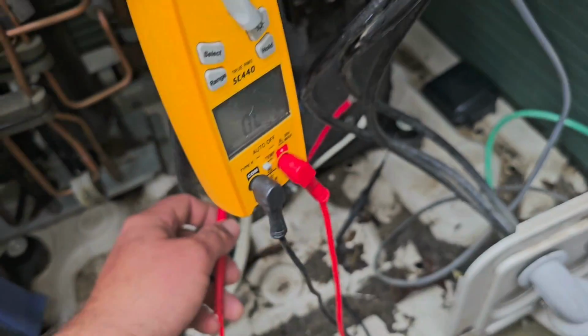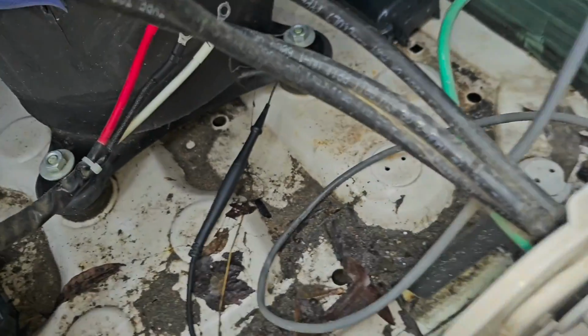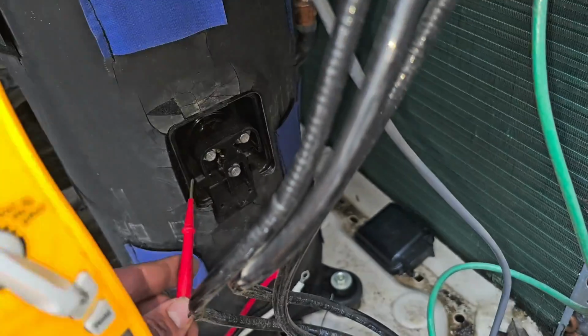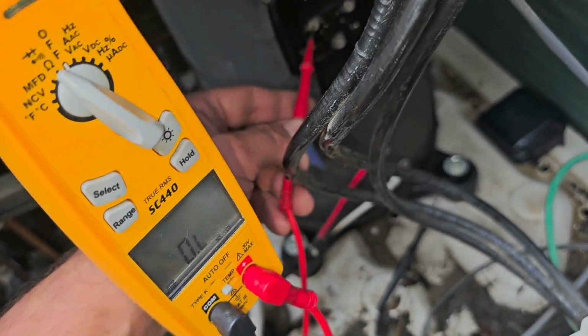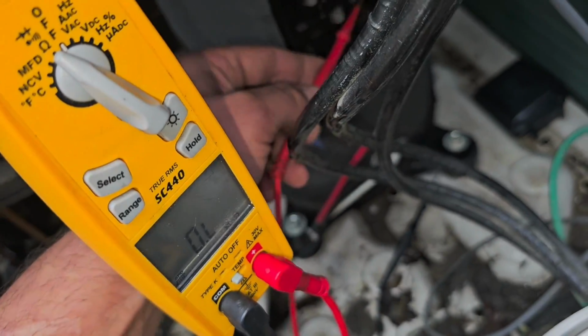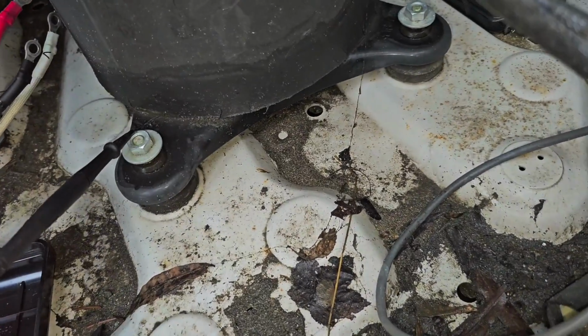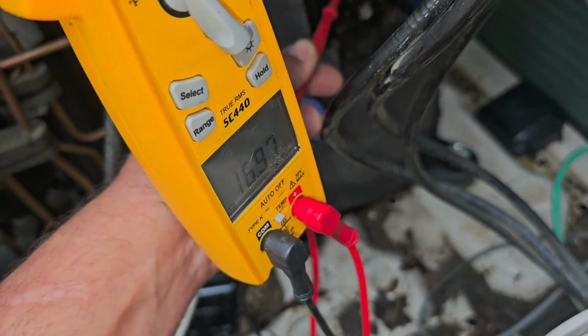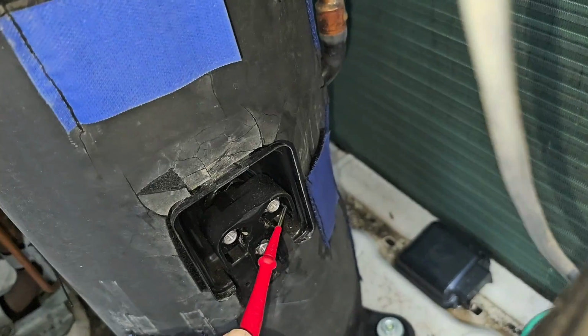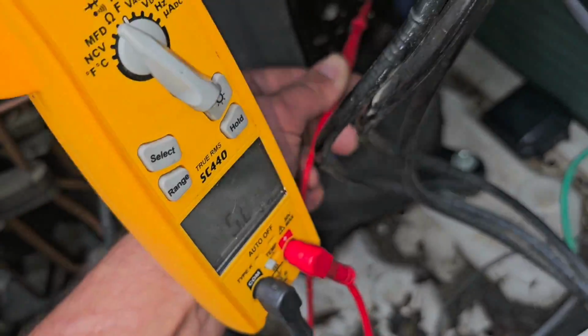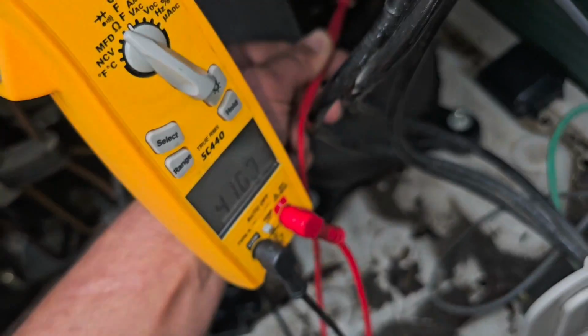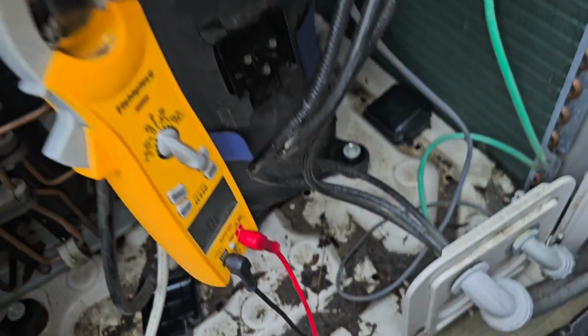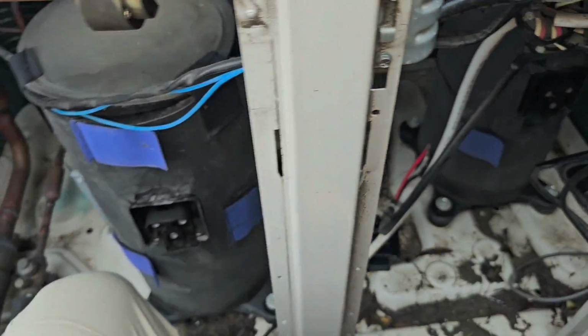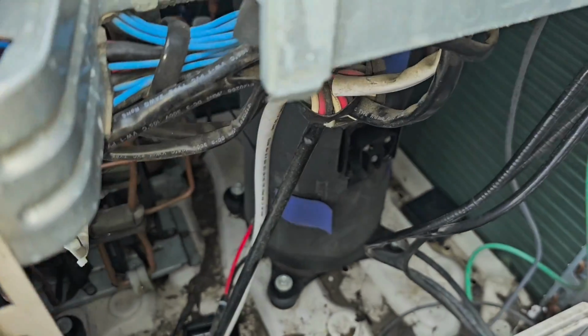Same thing for this compressor. Meter set to ohms. One lead touching the shell. And then let's see what we got. Same thing for this compressor. One lead touching the shell. Got the screws in, and we are going to check. Wow. Swap it. Yep. Last winding. Oh, there we go. Yep, shorted to ground. All right, I'm going to put it all back together, and then I'll be back with 2 compressors.